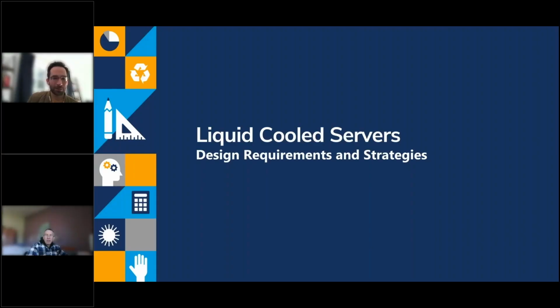Thanks, everybody. Brandon, there's a question here in the chat. What's the most common heating system, if any, for large server rooms? We're located in the Midwest, North, and high elevations where temps are often below 30 for extended time. I would say still no heating system for large data centers. Usually there's enough load, even if it's freezing outside, that say you had a system with an airside economizer, you would just be trimming the amount of outside air that you're bringing in and using a large fraction of recirculated return air to meet the load.